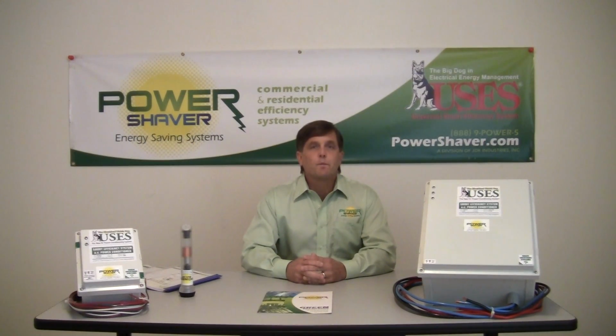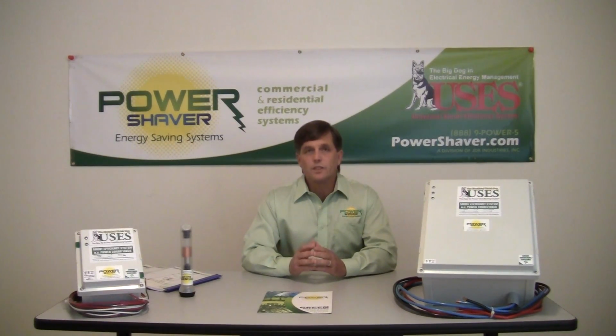The longevity is increased. Next, we incorporate passive resonance-free power factor correction. This is the reduction of the demand for VAR, volt amp reactance, or kVAR. This non-power current magnetic field is necessary for inductive loads to run. Our product provides that for you in a resonance-free manner by inducing this kVAR into the customer's conductors through magnetic chokes. This makes for a resonance-free connection, non-capacitive. So our product can be used with variable frequency drives and DC drives, any control systems, and will not cause any interference whatsoever.